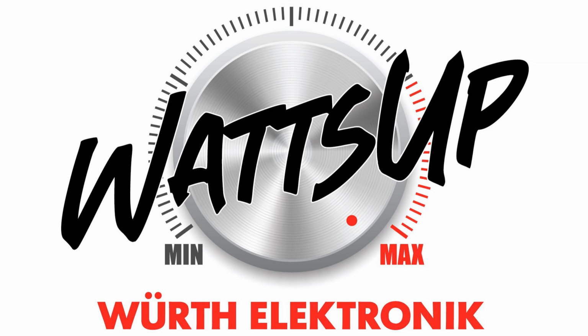So according to different international standards, there are different definitions which we can find in those standards. For example, the already mentioned 5 milliamperes for 2-second application of the voltage, or 3 milliamps for a longer period, for example, 5 seconds. Yes, and this maximum current must not be exceeded.